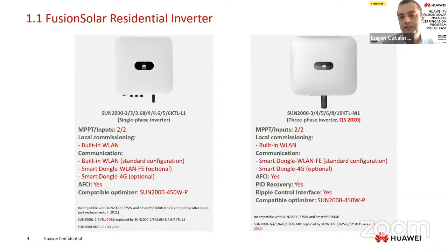Three-phase inverter, residential three-phase inverter, SUN2000-10KTL-M1, has also two MPPT and two inputs, but it has 1100 volts DC input. It generates a built-in WLAN, but only to connect locally on the inverter and set the inverter. Communication with FusionSolar on internet, of course, will be made through the Smart Dongle WLAN-FE that is in the package. It's standard in the package. Optional, if you want to connect with dongle 4G, you need to buy the dongle 4G.